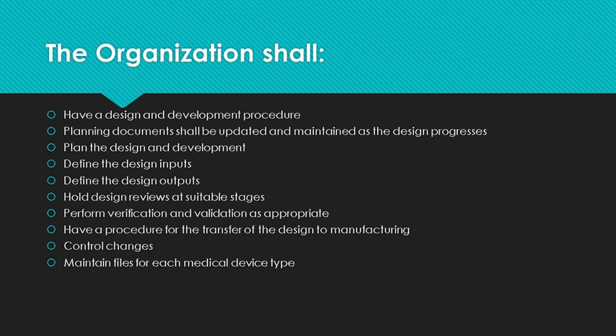Since ISO 13485 expects procedures, the documentation of the design process is a bit more direct. For starters, you should have a procedure for design and development. The elements of the process that should be documented are: plan the design development, define the design inputs, define the design outputs, hold design reviews at suitable stages, perform verification and validation as appropriate, have a procedure for the transfer of the design to manufacturing, control changes, and maintain a file for each medical device type.